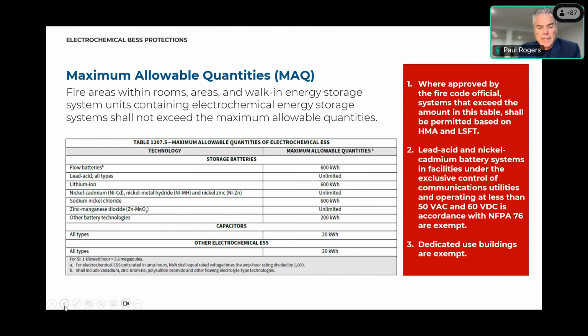Take a look at what we have with lead acid and nickel cadmium, they're unlimited. They've gotten sort of a way out of it because a lot of telecoms are using lead acid, and they've had a great track record. They also have to comply with another NFPA 76 number. I'm sure people are questioning why lead acid has unlimited allowance, and that's because these chemistries have actually been out there for a very long time with a great track record, so they gave them some leeway. You can move to the next slide please.